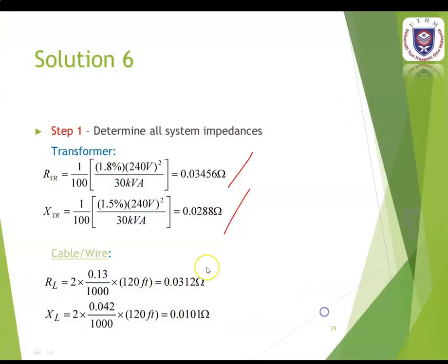After that, you use the single-phase equation to determine the resistance and reactance of the cable, which is 2 times the resistance or reactance per 1000 feet, times 120 feet. For the resistance you get 0.0312 ohms, while for the reactance you get 0.0101 ohms.